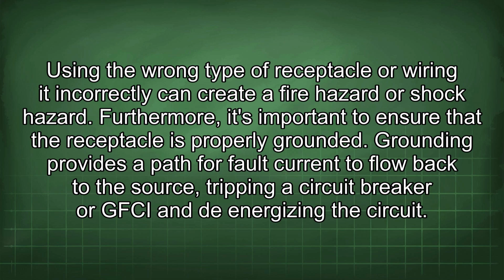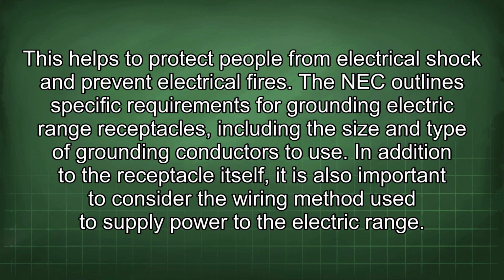Using the wrong type of receptacle or wiring it incorrectly can create a fire hazard or shock hazard. Furthermore, it's important to ensure that the receptacle is properly grounded. Grounding provides a path for fault current to flow back to the source, tripping a circuit breaker or GFCI and de-energizing the circuit. This helps to protect people from electrical shock and prevent electrical fires. The NEC outlines specific requirements for grounding electric range receptacles, including the size and type of grounding conductors to use.